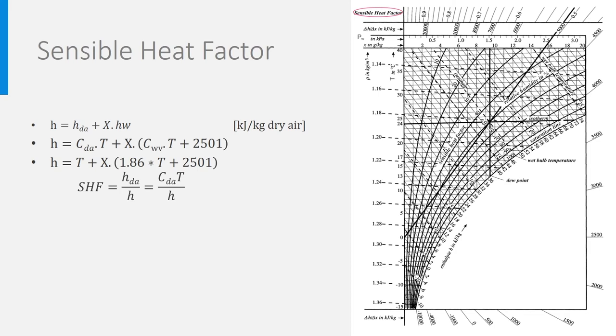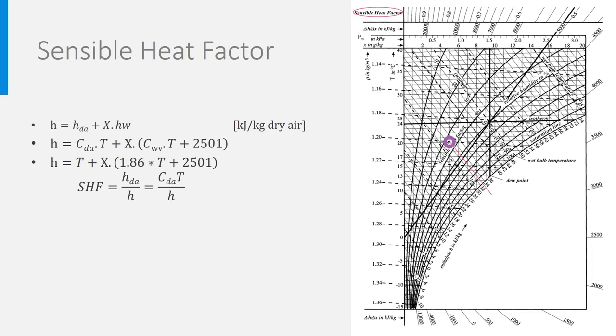Let's take an example of air at 20 degrees and absolute humidity 5 gram per kilogram. The enthalpy is then 32.7, you can calculate it like on the left or look at it on the diagram. To estimate SHF factor from the Mollier diagram, you just need to draw a line between dry air at 0 degree and the point for which you want to know this SHF and continue this line up to the axis with sensible heat factor SHF, where you can read the value of 0.61.